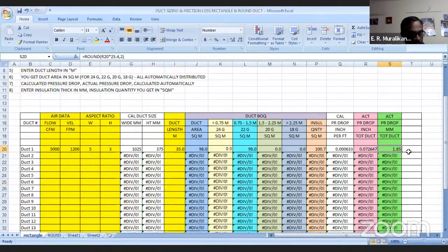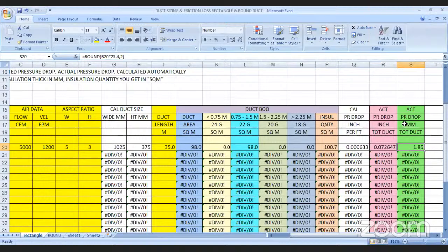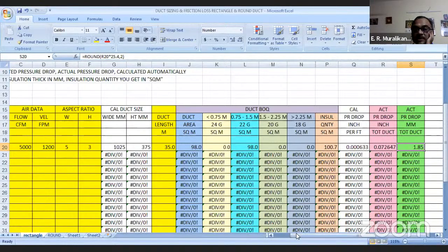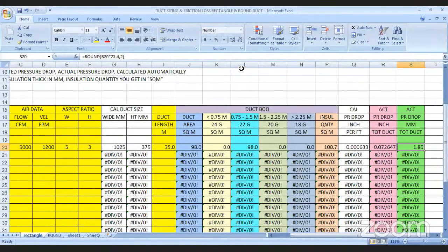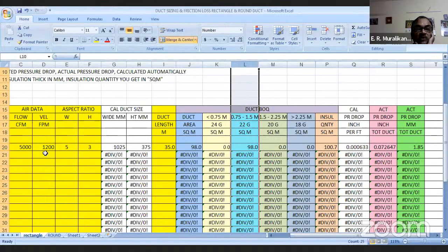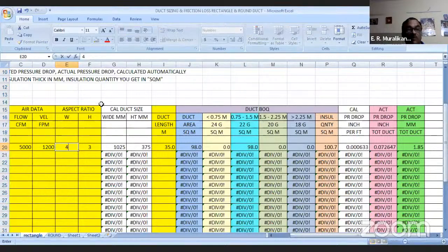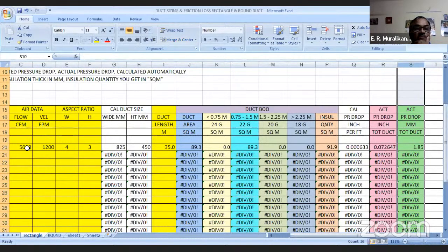Are you able to see here? Yes, sir. This is the pressure drop. Now since the size is big, it is now going for 22 gauge sheet. You are seeing here now. Aspect ratio, I told you how important it is. It is going to 22 gauge sheet for this duct. Now I am changing it to say 4 is to 3. Now see the actual pressure, how much is coming? 1.85. Now I am changing this velocity to say 1500. Now it's coming 3.26 pressure drop. You are able to see this now?